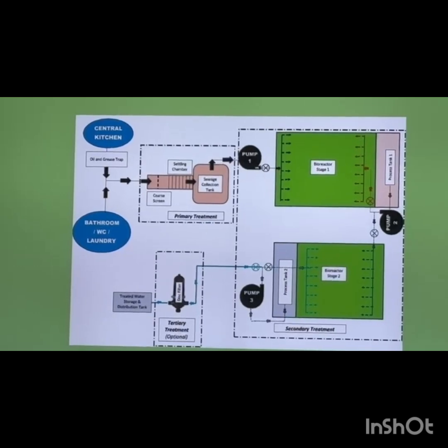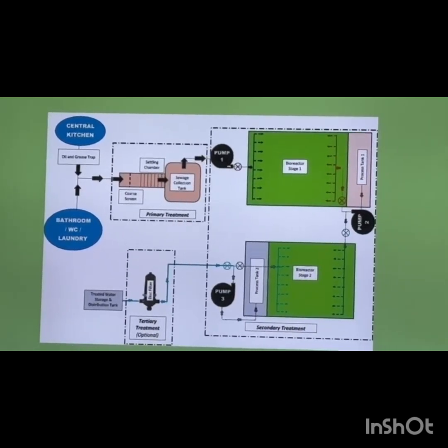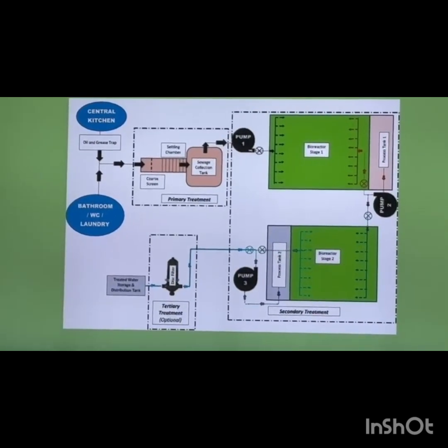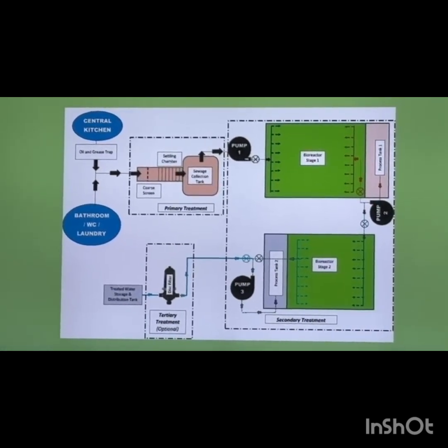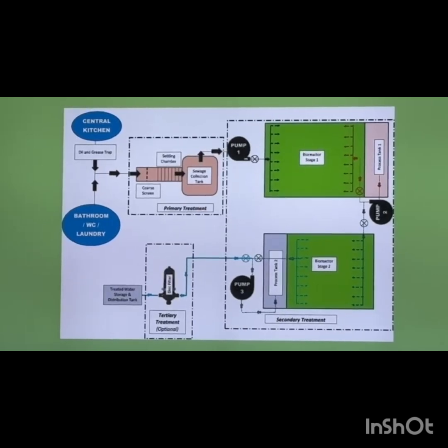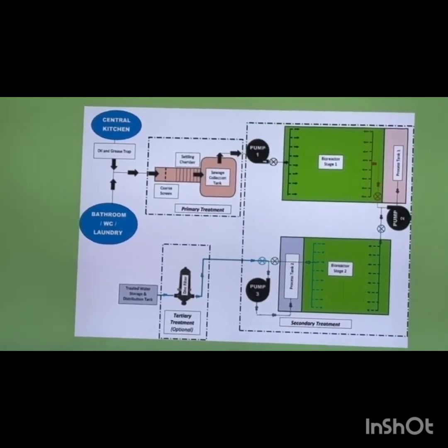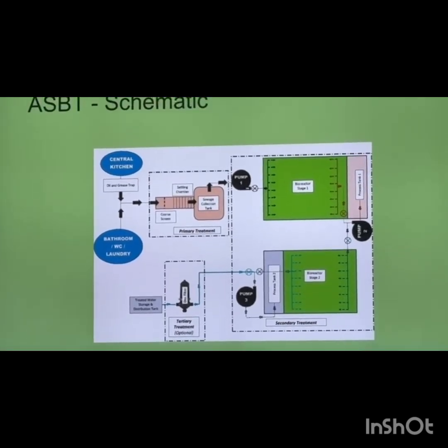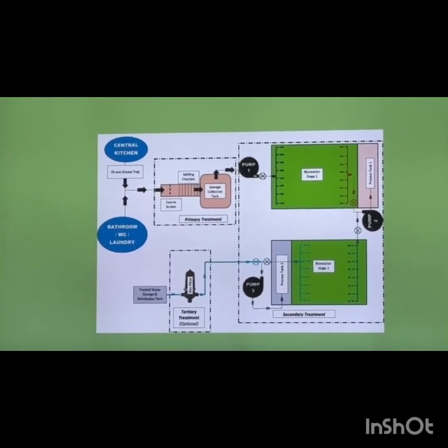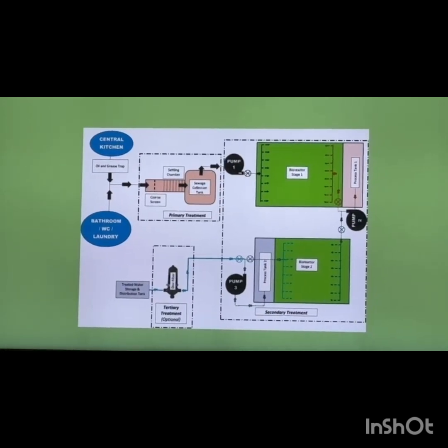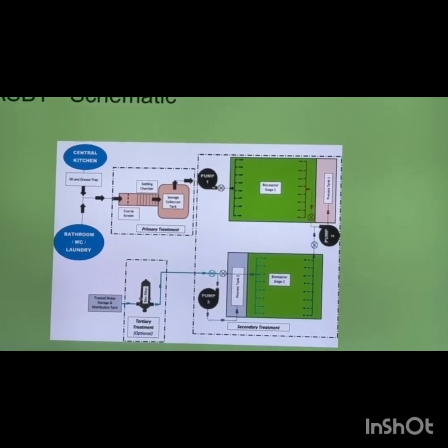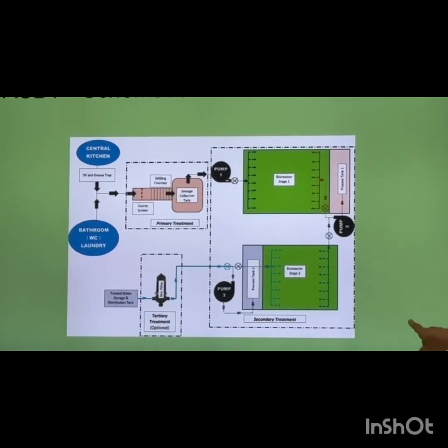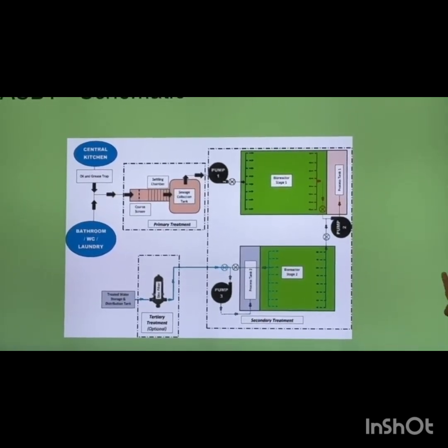So what we did, we got a reverse engineering done and we are fabricating so that it will automatically clear all the screen, I mean grids, floating material, everything in one drum screen. It has only a 0.5 horsepower motor rotating within a drum, and then automatically it is ejecting. You don't have to do the cleaning. Although it is common to all plants, these are the innovations we have done. Then there is a settling chamber. After the settling chamber, we are directly pumping into the bioreactor.